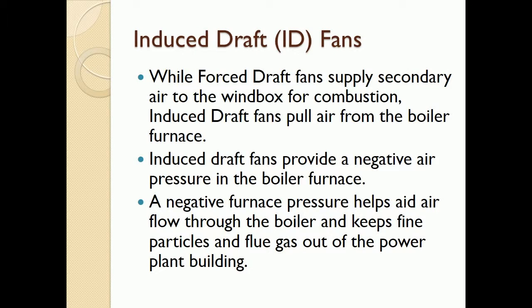Induced draft, ID, fans. While forced draft fans supply secondary air to the windbox for combustion, induced draft fans pull air from the boiler furnace. Induced draft fans provide a negative air pressure in the boiler furnace. A negative furnace pressure aids the air flow through the boiler and keeps fine particles and flue gas out of the power plant building.